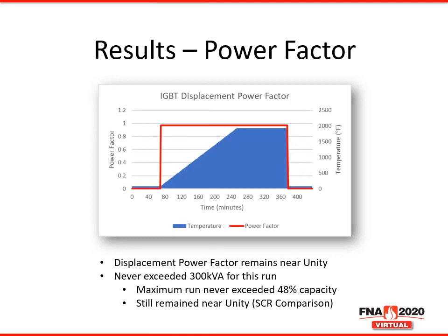Finally, let's examine the displacement power factor. This graph is similar to the previous two, but on the left y-axis, we're looking at displacement power factor. A good displacement power factor is close to 1. That means that power is being delivered most efficiently to your system. As a power factor gets lower, it can incur penalties and other complications for the facility. This is why some customers will use a capacitor bank in the facility for correction. You can see that with the IGBT MFDC power supply, the power factor remains near unity throughout the entire cycle. If you were to compare this to a phase angle control, as the power drops down and we go to a lower set point, you would see a lower power factor.